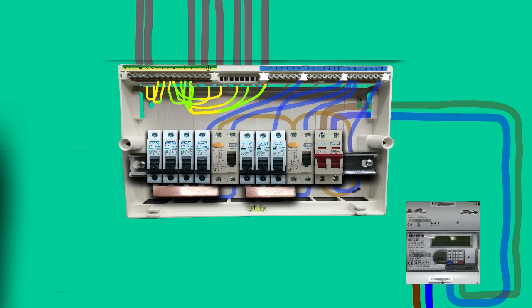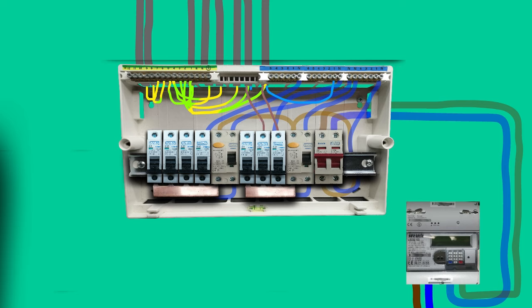Now let's do the line and neutral conductors from each cable. So the line conductor from the first cable goes to the L-terminal on the 40A MCB. This is probably some shower circuit. The neutral conductor from the first cable goes to terminal 1 on the second section in the neutral bar. Line from the second cable goes to the next MCB, neutral to the number 2 terminal and the same with the third cable. And we've got the first three circuits wiring completed.